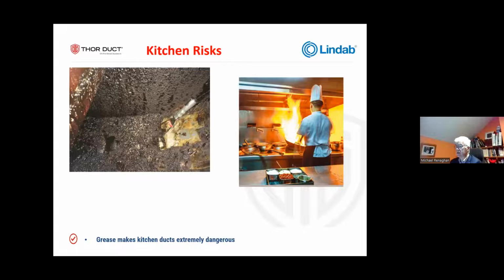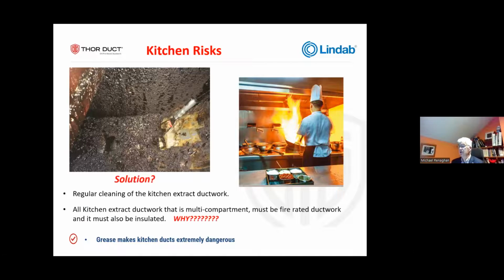So the solution for kitchen extracts, the obvious solution, is regular cleaning of the kitchen extracts. However, there's no regulation per se that demands that you must clean your kitchens. So the insurance industry and other industries are pushing for this and trying to make it mandatory. However, if you don't clean them, which is what's going to probably happen, or if you do clean them on a regular basis, there's always going to be some dirt the day before you clean them. The risk is that there could be a fire.